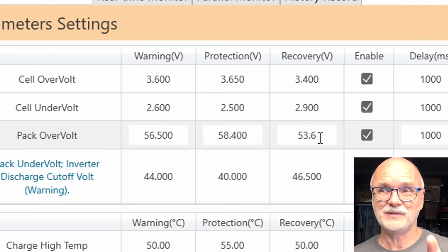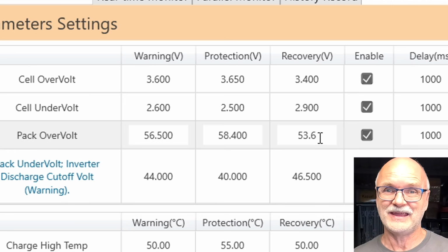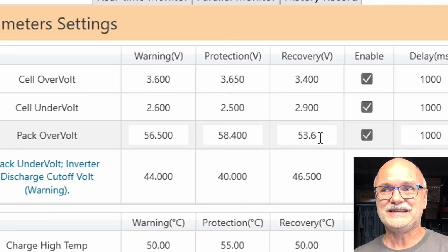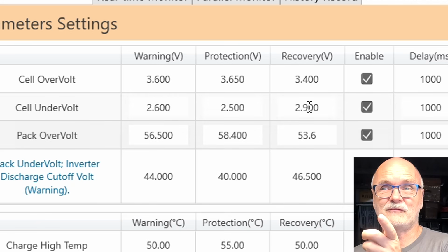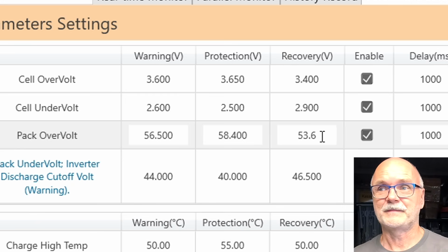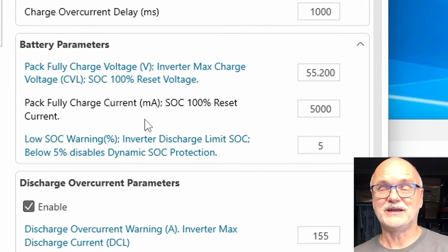This is a very similar mechanic to what we have in the JK inverter BMS, but there we can set all the parameters separately and individually, so it's clearer what it actually does. Here it's all very hidden - there's no additional text in the software saying this recovery voltage is also your float voltage, and that once the BMS resets, we stay at 55.2 volts for 1 hour. It doesn't say that anywhere.